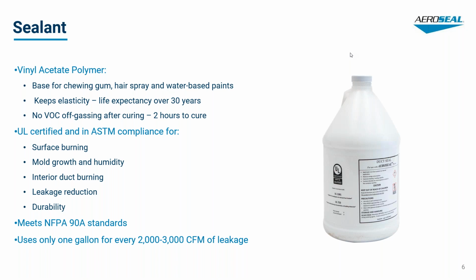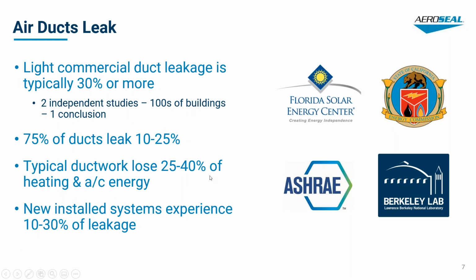So why do we use Aeroseal? Well, it's because air ducts leak, and that's no surprise to anyone on the call. There have been multiple studies showing that light commercial duct leakage is typically 30% or more. ASHRAE says 75% of all ducts leak between 10 and 25%. Typical ductwork will lose 25 to 40% of its heating and air conditioning energy. Even newly installed systems experience 10 to 30% leakage.